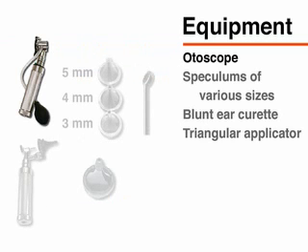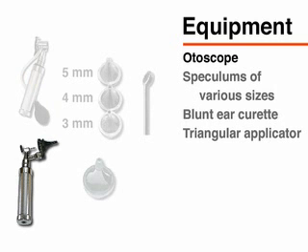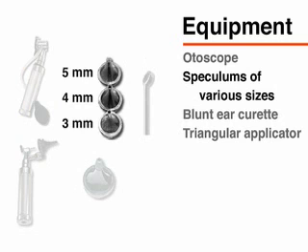For pneumatic otoscopy, you will need an otoscope with a diagnostic head that has an attached rubber bulb and a movable lens. Cerumen removal is most readily accomplished using an otoscope with a surgical head, but a diagnostic head may also be used. You should use the largest otoscopic speculum that fits comfortably into the external auditory canal; for very large canals, soft tip speculums may be needed.